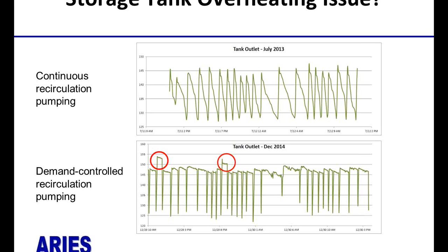And this is because the water in the tank is stratifying. The hot water is coming in from the boiler to the top of the tank. It's less dense and it's staying there at the top of the tank. And as the makeup water, which is more dense, comes in at the bottom of the tank, it stays at the bottom. And without the pump to circulate it back and forth, as the tenants draw water, it comes from the top of the tank.